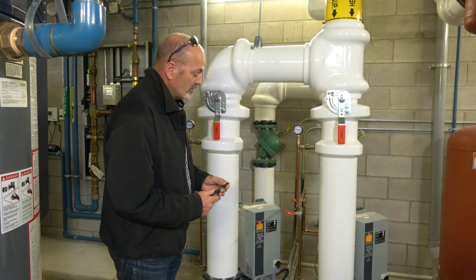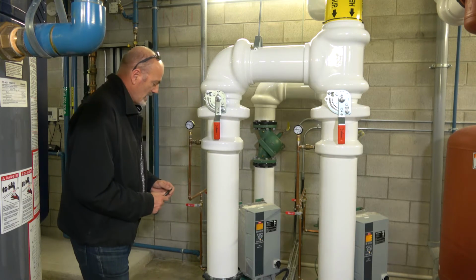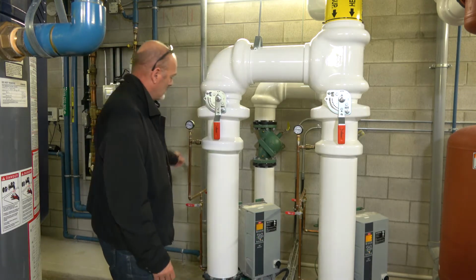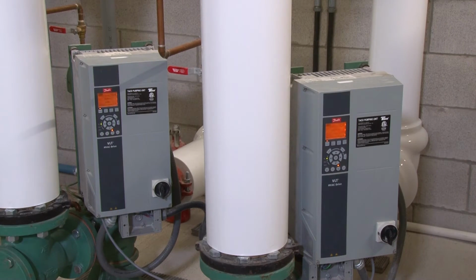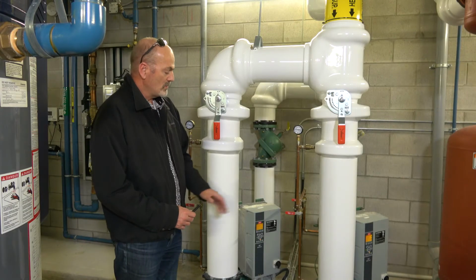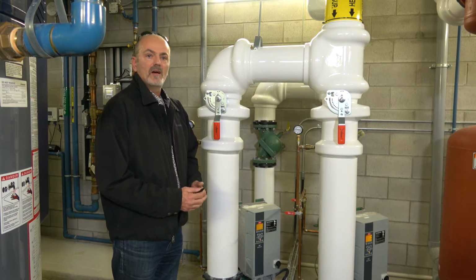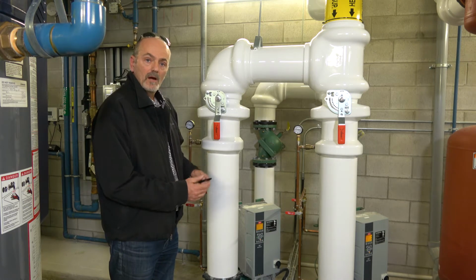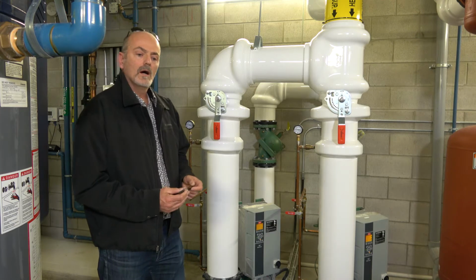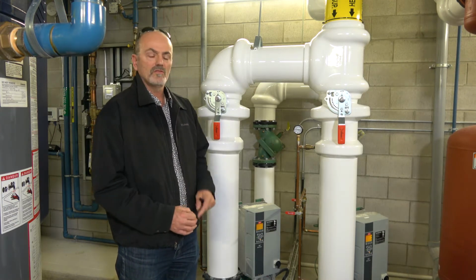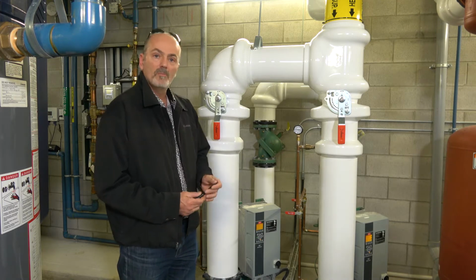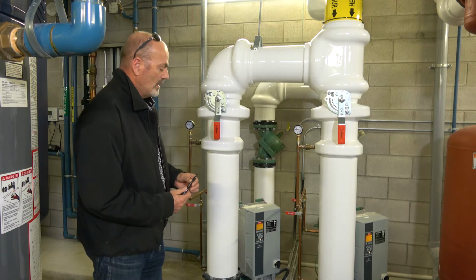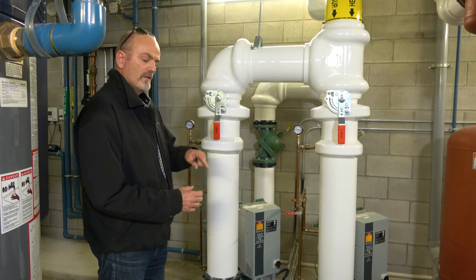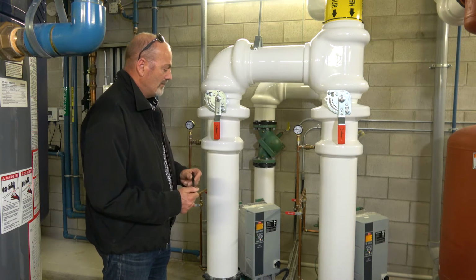Okay. In terms of control and maintenance of these products and understanding them, they're what's called a vertical inline pump. The motor is above the pump end. They're close coupled, so there's no coupling, but the motor shaft is the pump shaft, and it's attached to the impeller inside the pump as it spins. There is a seal kit between the motor end in the cover plate and the pump that separates the water from the ambient air around the pump. That seal basically is a stationary surface and a rotating surface, and they spin at a high rate of speed. Whatever the speed of the pump is the rate of RPM on the seal. The intent of the seal is to allow for that movement between the two faces and RPM, but not allow leakage of water.